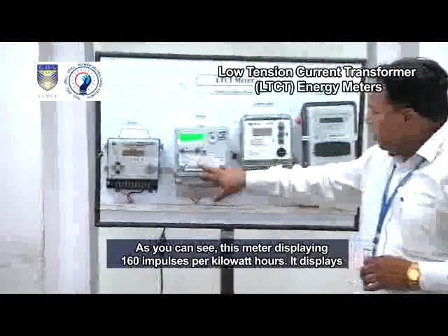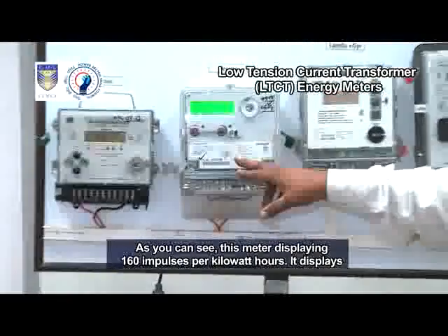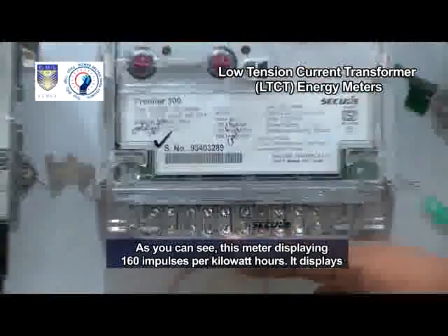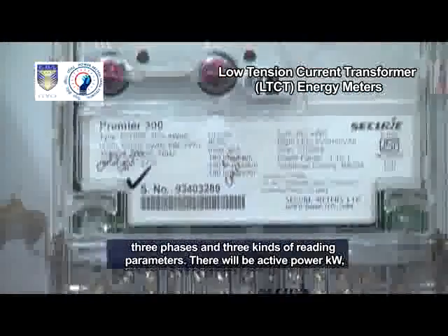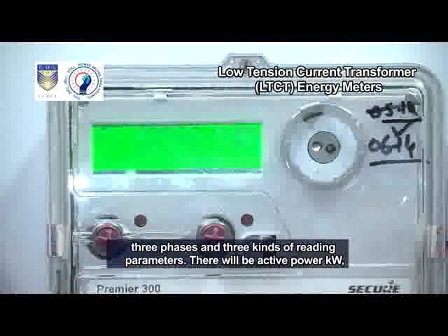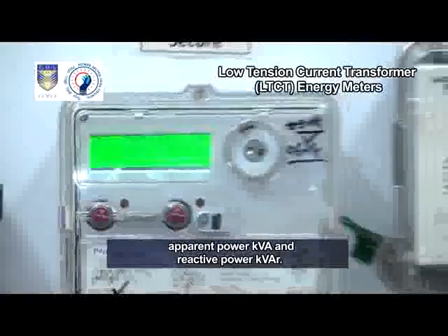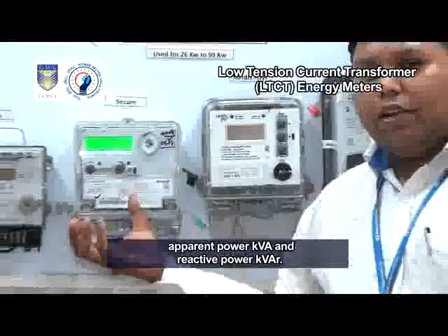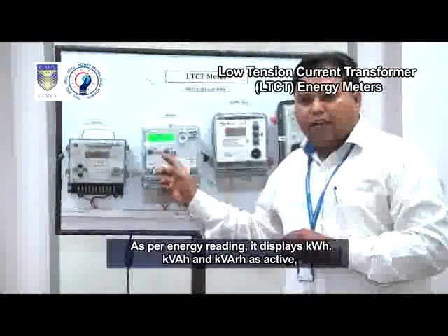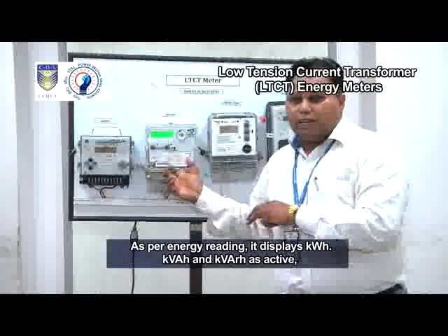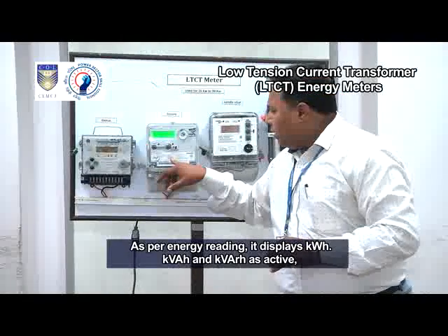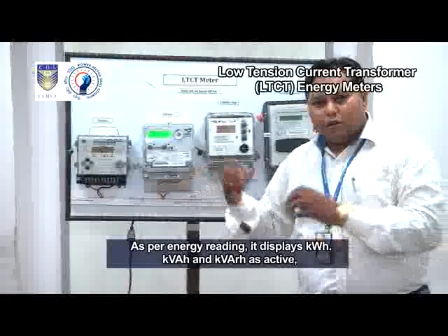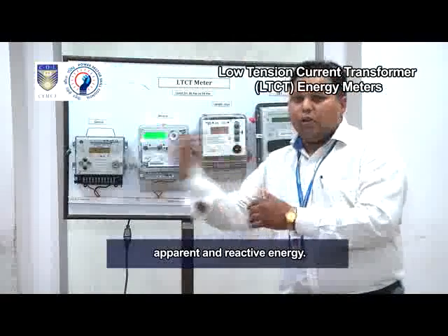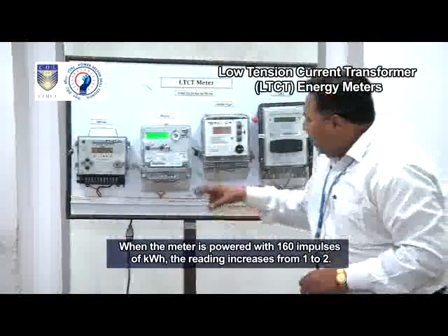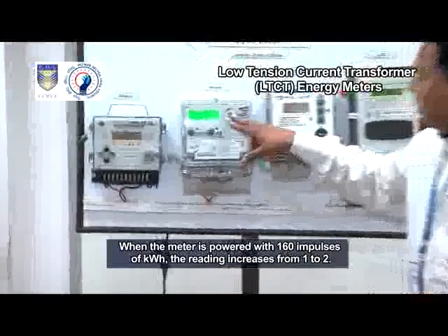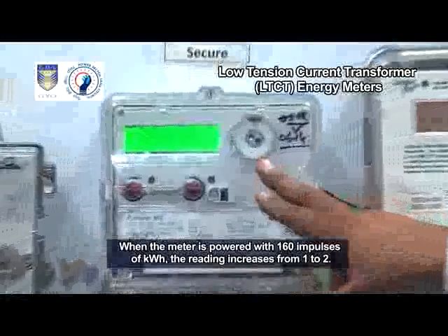As you can see, this meter is displaying 160 impulses per kilowatt hour. It displays 3 phases and 3 kinds of reading parameters. There will be active power kW, apparent power kVA, and reactive power kVAR. As per energy reading, it displays kWh, kVAh and kVARh as active, apparent and reactive energy. When the meter is powered with 160 impulses of kilowatt hour, the reading increases from 1 to 2.